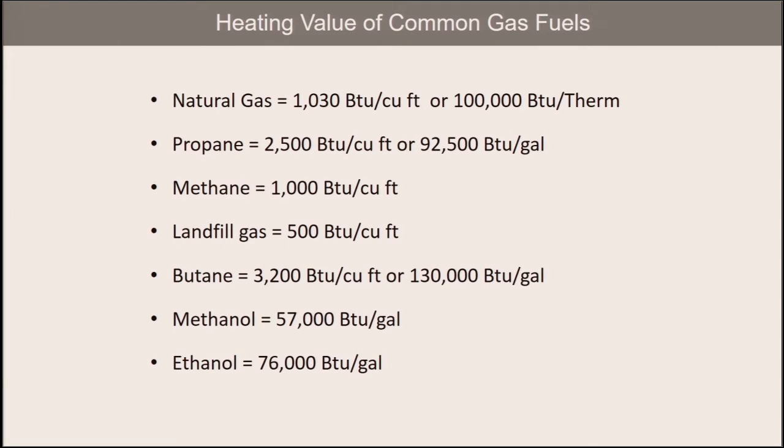The most prominent of the fuels burned today is natural gas, and that's why I have it listed first. And as you can see, it releases about 100,000 BTUs per therm, a therm being 100 cubic feet, and a cubic foot of gas being about 1,000 BTUs.